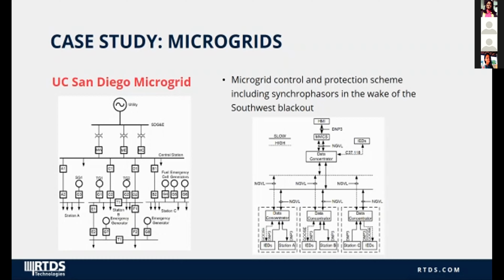During the 2011 blackout in the southwest United States, this microgrid disconnected from the main grid, but it didn't shed load quickly enough, so their cogenerators shut down due to those critical loads. They have since modified the microgrid.